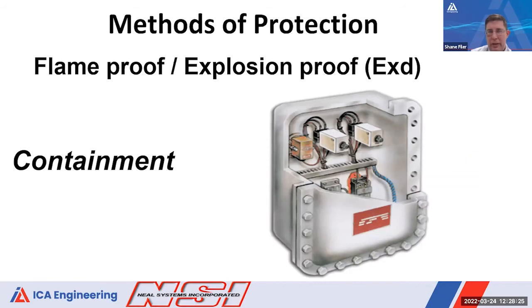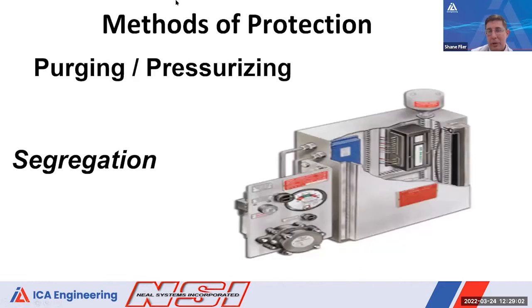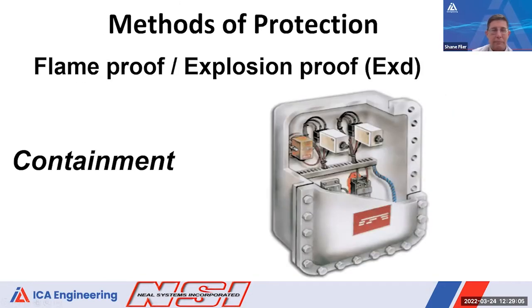One thing, if you can stay on that slide just a second there, Joe. One fun thing when I teach, I like to ask the question: have you ever had one of these panels, as you see here, where people have sawed off the bolts and super glued them on, or just had the corner ones on and forgotten all the rest? And have you ever had the conduits, what they fed into there, not filled correctly? Almost everybody looks around at each other, and then they all raise a hand slowly, because they've all seen it at their plants. Because there isn't a good enough teaching on some of this, they end up causing other problems. So it is an issue you've got to worry about.